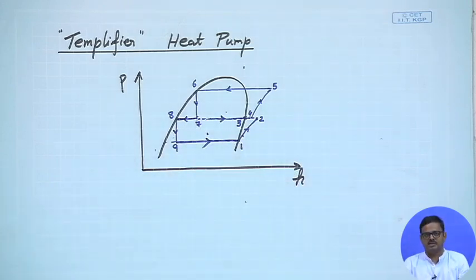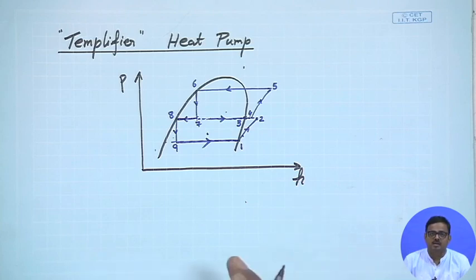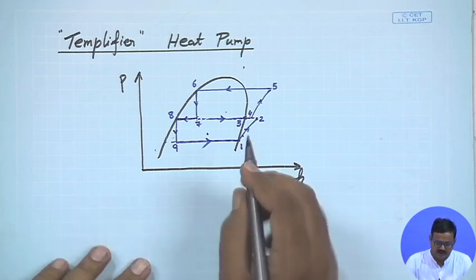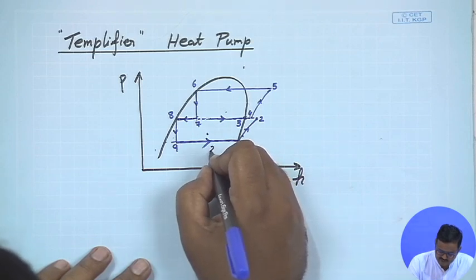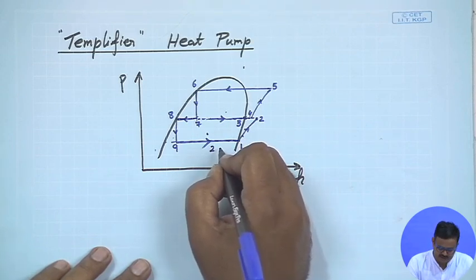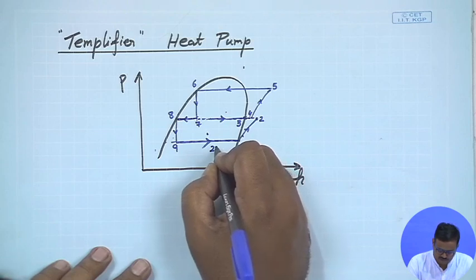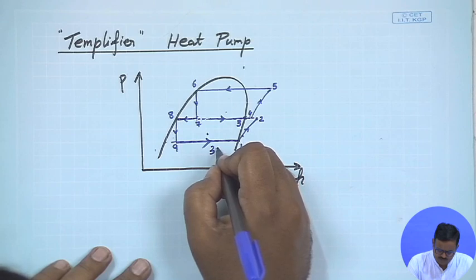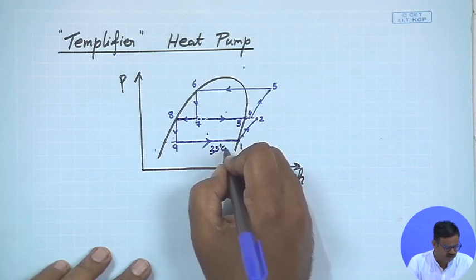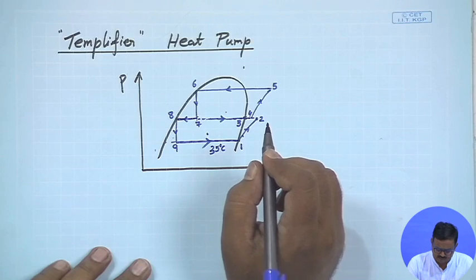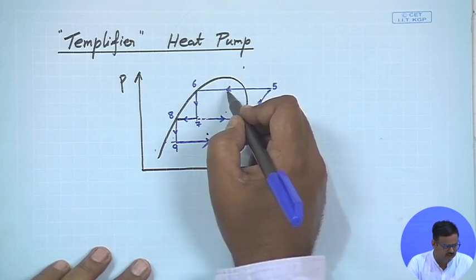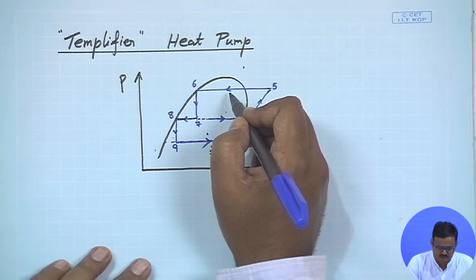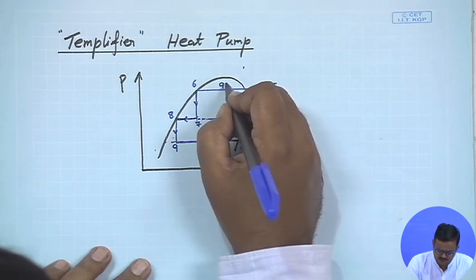Okay. So, this is the refrigerant cycle which is going through this, all right. The two stage compression is required, because in the templifier unit the temperatures that we have at the evaporator over here, it is around I believe 35 degrees, and over here the temperature, because it is giving up heat, is almost about 90 degrees or so.